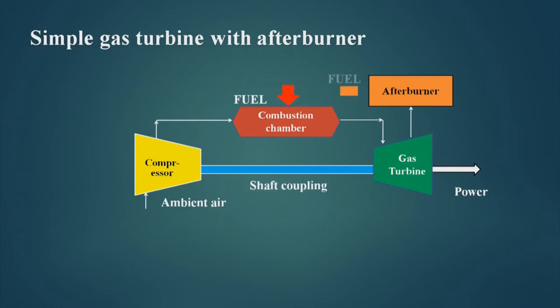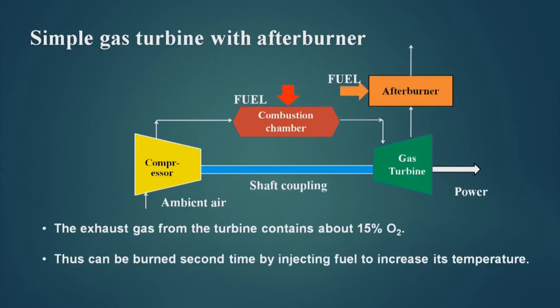Another type of gas turbine has an after burner. The concept is that if the temperature of the exhaust gas from the gas turbine is low, we can increase its temperature using an after burner. We are trying to regulate the hot flue gas temperature using different techniques. One technique uses the recuperator to bring down the temperature of the hot flue gas while increasing efficiency and decreasing fuel consumption. If we want to increase the hot flue gas temperature, we can use the after burner. The exhaust gas from the turbine contains about 15 percent oxygen, so we can add fuel to it and re-burn it to increase the temperature of the exhaust gas.